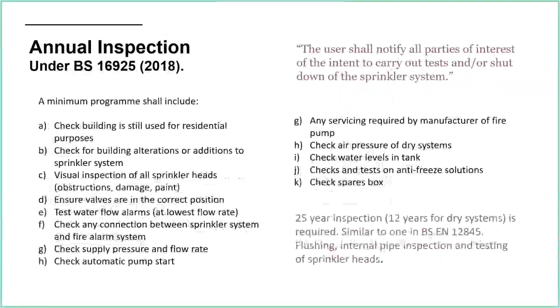Just comparing that now to 16925, I missed out the EN there, so that's BS EN 16925 in 2018. Again, minimum program. It's another annual inspection, but as a minimum. Very similar. I'm not going to go through it all, but you can see that it's a very similar setup to the 9251. They specifically talk about an automatic pump start, but that will be done under 9251 as well. They talk about having a spares box. I'm not sure 9251 insists on having a spares box, whereas 16925 does. That was a good statement I found there.